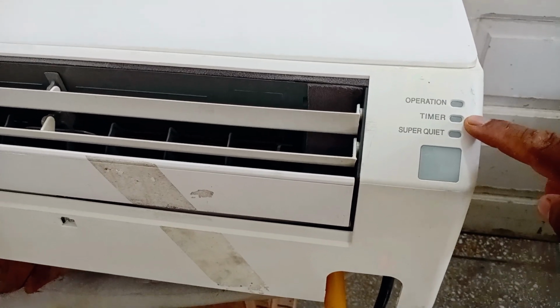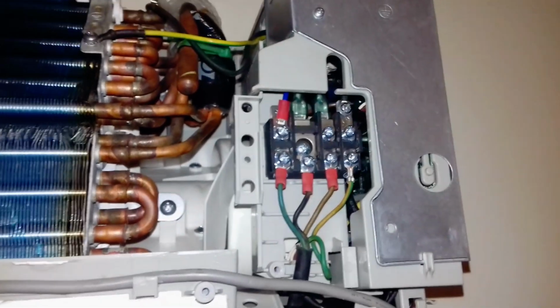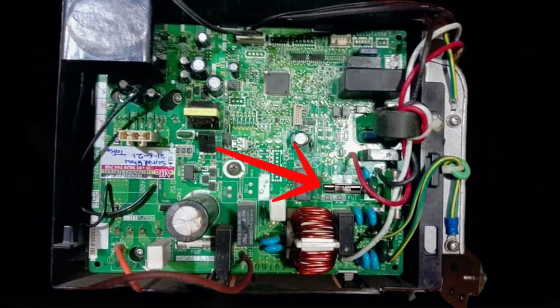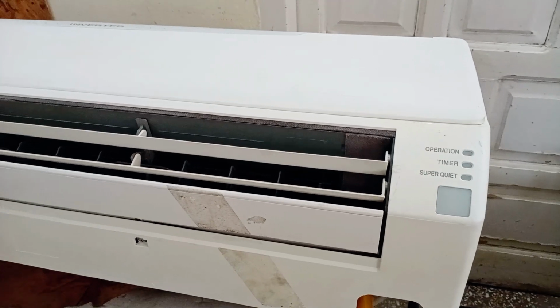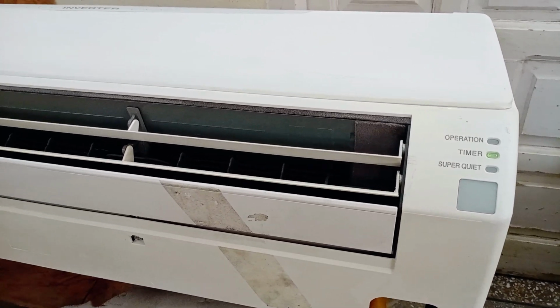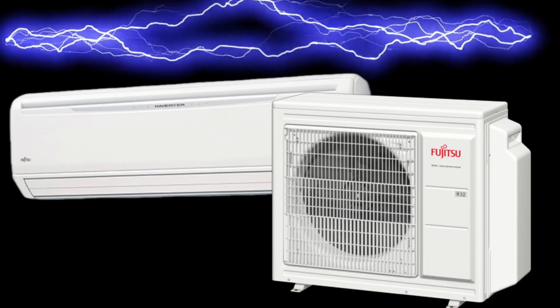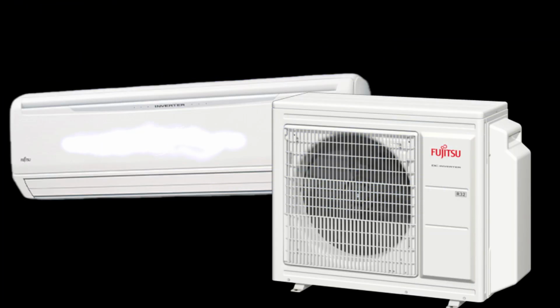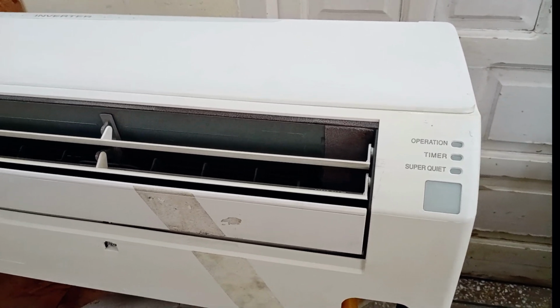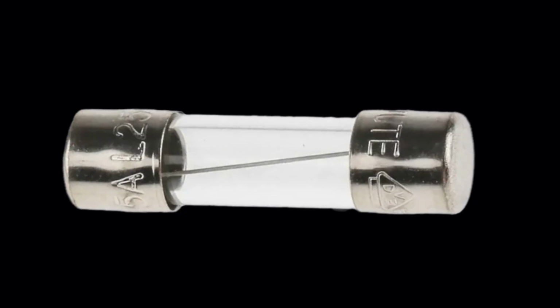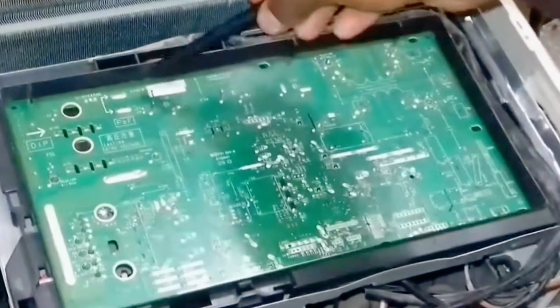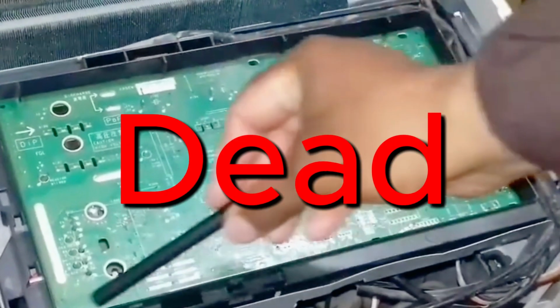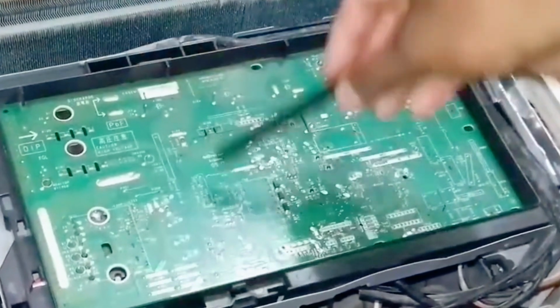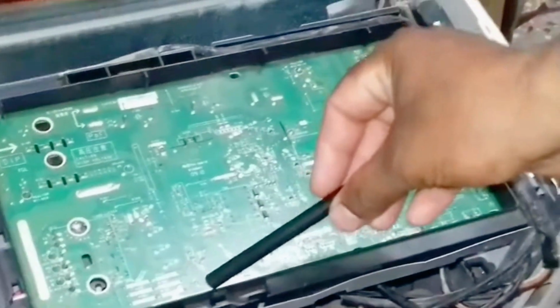To solve this issue, you should check the connections of the wires. Check the fuse on the outdoor circuit board. In these models of General or Fujitsu air conditioners, the electricity flows from the outdoor unit to the indoor unit. So, if power is not reaching the indoor unit, it means that the fuse on the outdoor circuit board might have blown, or the entire circuit board is dead. In this case, you will need to either repair or replace the circuit board.